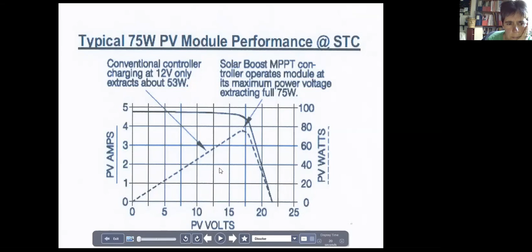More recently, people have been using what's called a maximum power point tracker, a box of electronics that converts power at one voltage to power at a different voltage. So maybe your battery is at 12 volts, say it's recently been discharged, whereas your panel's best voltage is at 17 or 18 volts. It absorbs power from the PV module at that voltage and gives it out to the battery at a lower voltage, so less voltage but more current.